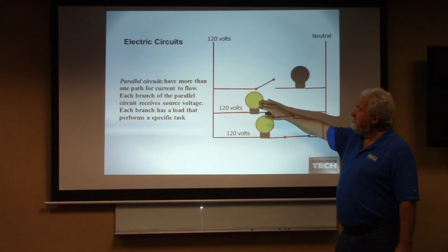Total amps of the circuit are the sum of the individual amps measured by each branch. Well, wait a second. If this was my crankcase heater, how many amps am I reading on my crankcase heater? How much current is going through this circuit right now? So how many amps am I going to read on that circuit? 0. On my compressor, how many amps would I see on that circuit? 15, okay, 15 amps. What would I see on my fan motor circuit? 2. So if I had 2 here, 15 here, and 0 here, what would I measure on the line coming into that? 17 amps. So my amperages add up in parallel, is that right? I only had 1 amperage in series, but in parallel they add up.